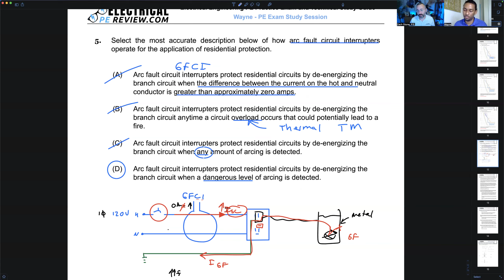AFCI would show. Okay. If I was taking the PE exam tomorrow and had a problem like this that just talked about de-energizing due to arcing, but there weren't two similar questions where one says any arcing and the other says dangerous levels, if I just had one choice that talked about interrupting due to arcing, I would pick it. But here it's a little bit of a trap, because they're not designed to trip for any amount of arcing, because that's part of using 120 electricity. There's always going to be some level of arcing, but it's so tiny that it's not really going to hurt anything. Arcing at higher voltage levels is a way different story.